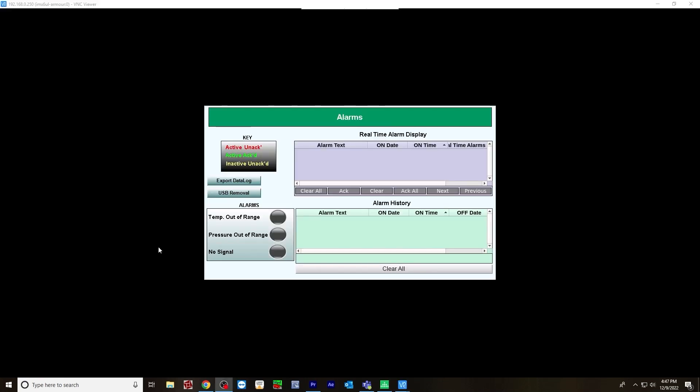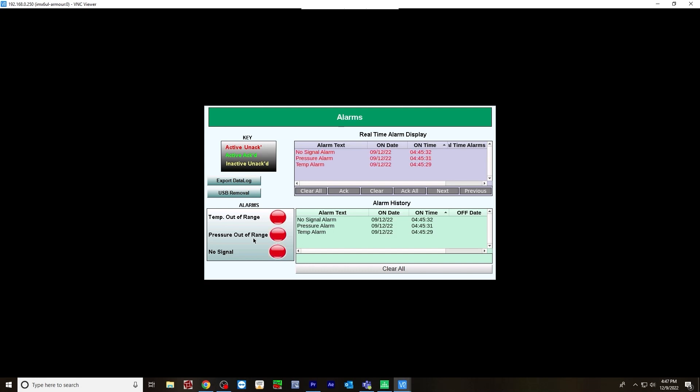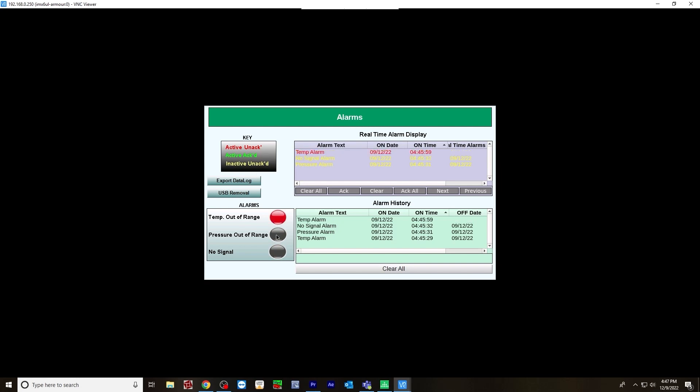After you download and go online, I now have VNC viewer open to view the user interface on the HMI device. We're viewing the base screen that we created. Now I'm going to first trigger some alarms: temperature out of range, pressure out of range, no signal. And you can see they all show up in the real-time display and alarm history. They are labeled red as active unacknowledged alarms. If we were to turn these off without acknowledging them, they turn yellow, which is inactive unacknowledged.